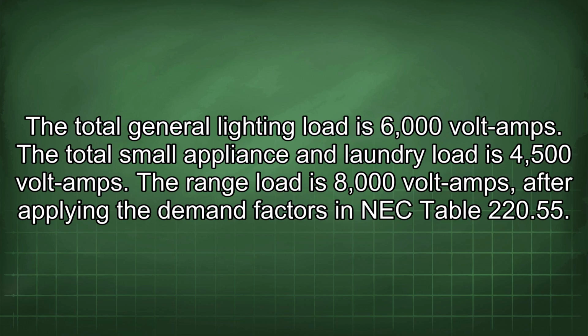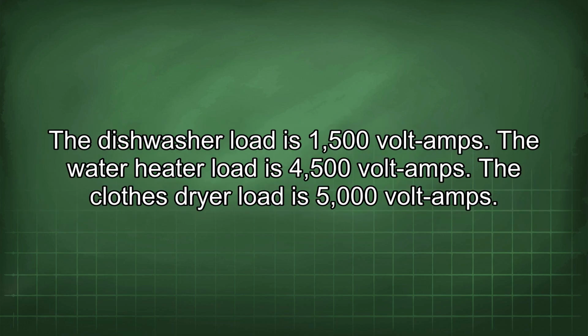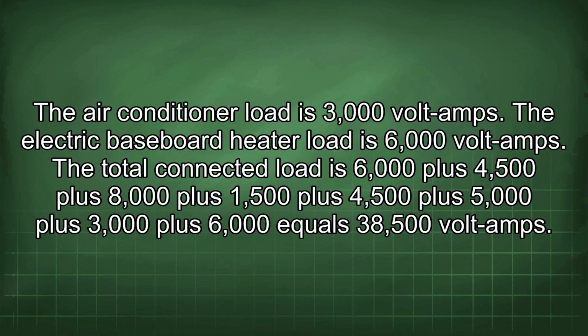The total general lighting load is 6000 volt amps. The total small appliance and laundry load is 4500 volt amps. The range load is 8000 volt amps after applying the demand factors in NEC Table 220.55. The dishwasher load is 1500 volt amps. The water heater load is 4500 volt amps. The clothes dryer load is 5000 volt amps. The air conditioner load is 3000 volt amps. The electric baseboard heater load is 6000 volt amps.